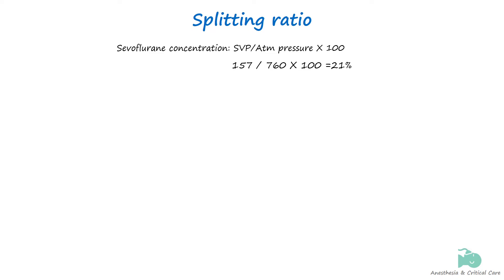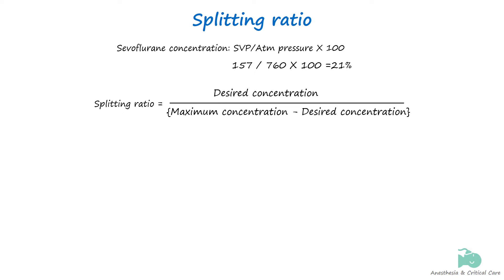To achieve a 2 percent concentration of sevoflurane, the splitting ratio can be calculated using the formula. Plugging in the values, we get a splitting ratio of 0.11. This means that approximately 11 percent of the fresh gas flow will pass through the vaporizing chamber to pick up sevoflurane, while the remaining 89 percent will bypass it.